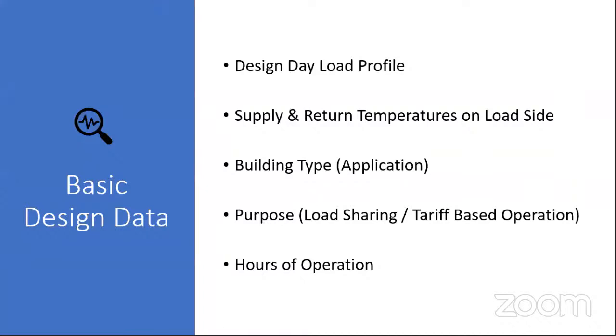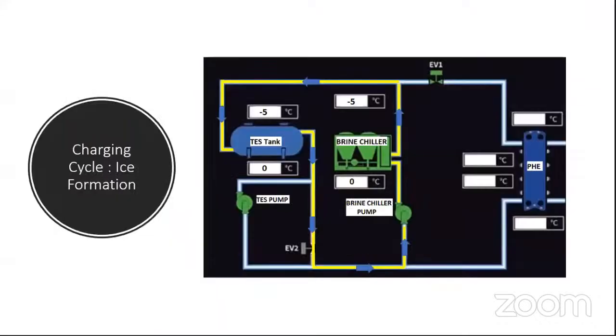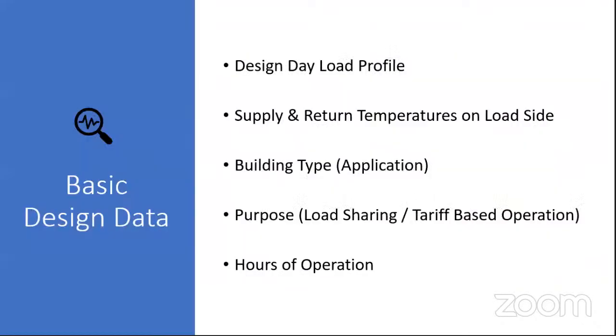Important design considerations. We just saw the schematic and understood how it operates in general. For designing, we need the design day load profile. We need the supply and return temperatures on the load side, like we saw previously, 7 and 12. We also need to know the building type, the application, from the space perspective, or where they want to place them.